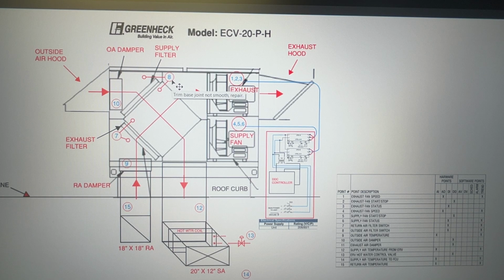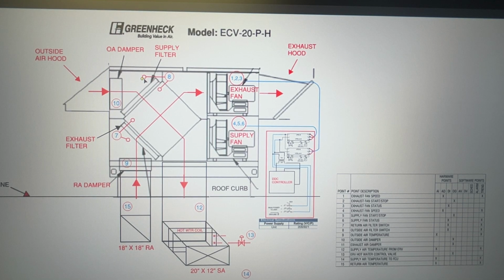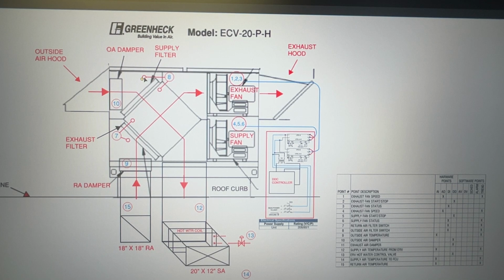Point 8 is going to be our filter switch, which is going to show what the difference is on each side of the filter so that you know when you need to replace those filters. On the exhaust filter, you have the same thing. You have another point on each side of that filter so that you're aware of when those need to be replaced. Point 9 is your return air damper. That obviously opens and closes as the unit runs. Points 1, 2, and 3 here are your fan speed, start and stop operation, and its status. 4, 5, and 6 are the same just for the supply fan. So you've got your fan speed, start and stop, and then your status.